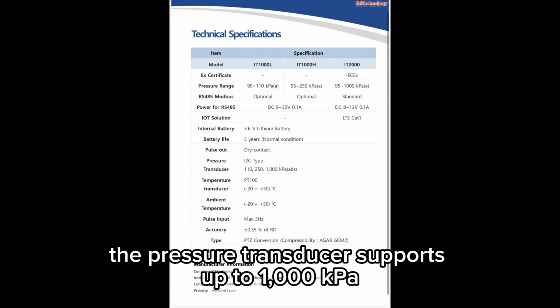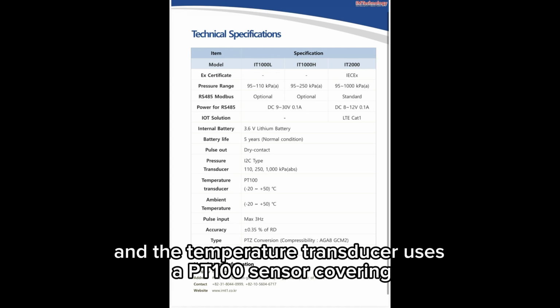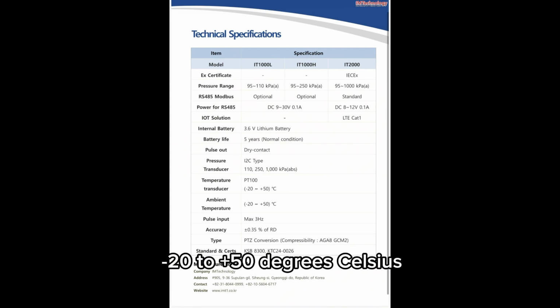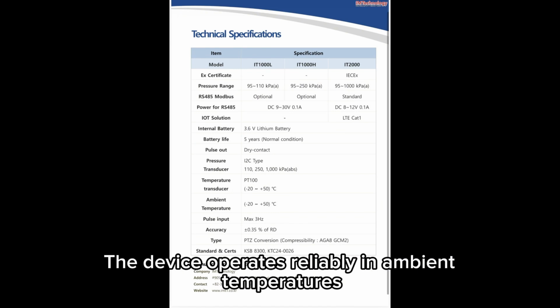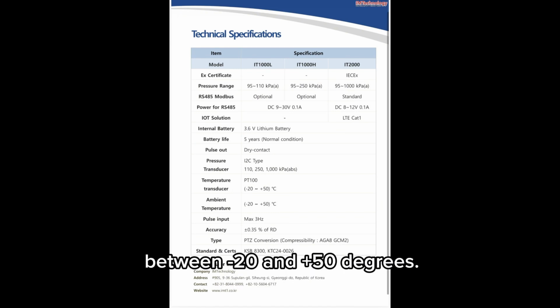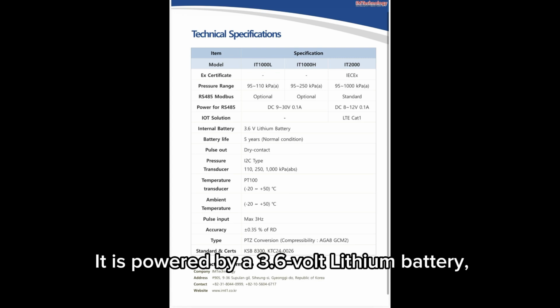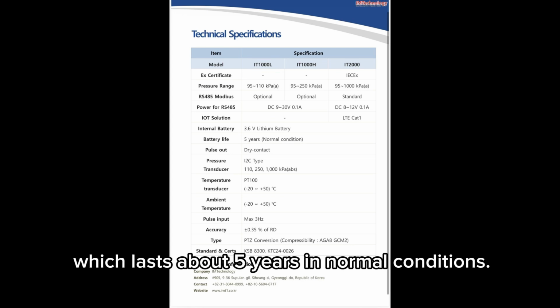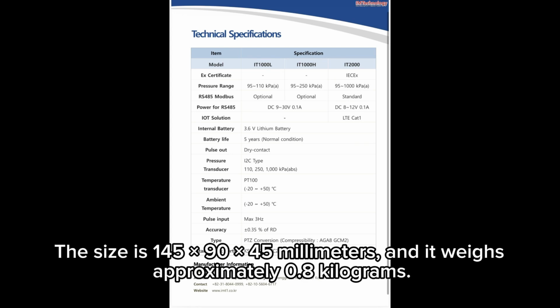The pressure transducer supports up to 1000 kilopascal, and the temperature transducer uses a PT100 sensor covering -20 to +50 degrees Celsius. The device operates reliably in ambient temperatures between -20 and +50 degrees. It is powered by a 3.6-volt lithium battery, which lasts about 5 years in normal conditions. The size is 145 by 90 by 45 millimeters, and it weighs approximately 0.8 kilograms.